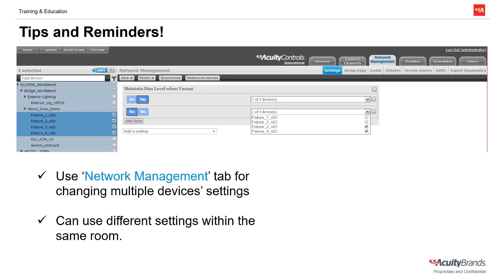A couple tips and reminders to keep in mind when programming NLIGHT output devices. Remember to use the Network Management tab when we want to change the behavior of multiple devices. Usually when we're changing these settings, we're having to change multiple — sometimes even hundreds of devices at a time — and we can accomplish this easily with the Network Management tab using the checkboxes for each device we wish to modify.